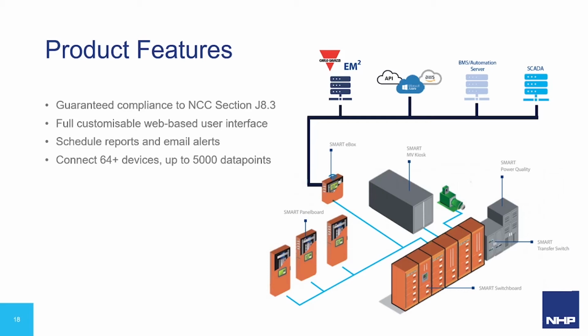As I said before, you can connect 64 or more devices, or 5,000 data points, to any single Smart eBOX. The eBOX can pull data from any Modbus capable device, including our panel boards, switchboards, transfer switches and power quality units, just to name a few.